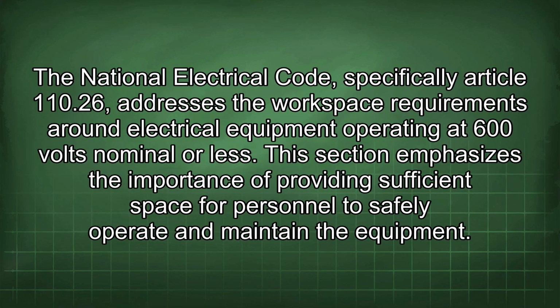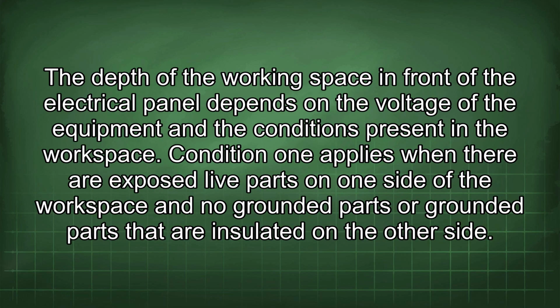The National Electrical Code, specifically Article 110.26, addresses the workspace requirements around electrical equipment operating at 600 volts nominal or less. This section emphasizes the importance of providing sufficient space for personnel to safely operate and maintain the equipment. The depth of the working space in front of the electrical panel depends on the voltage of the equipment and the conditions present in the workspace.